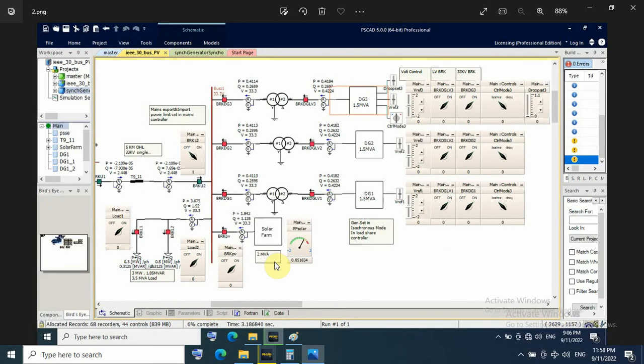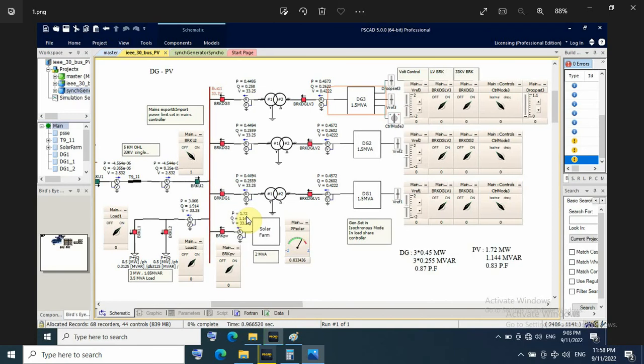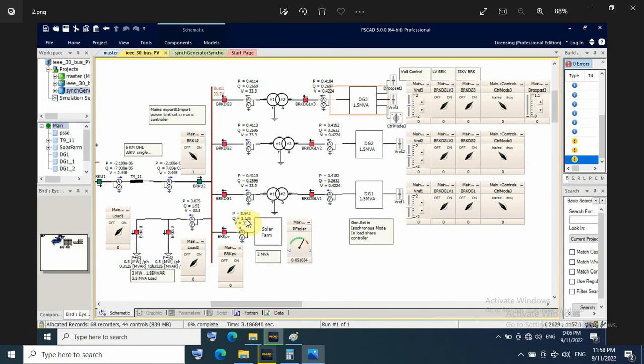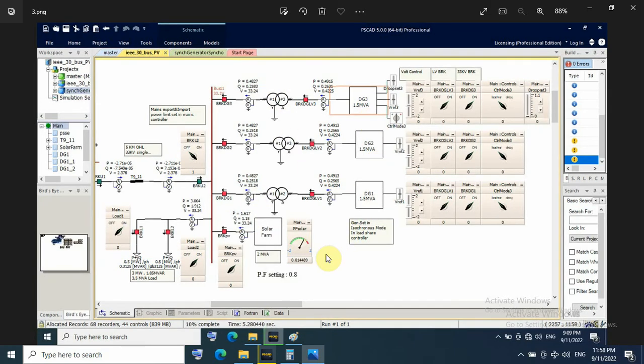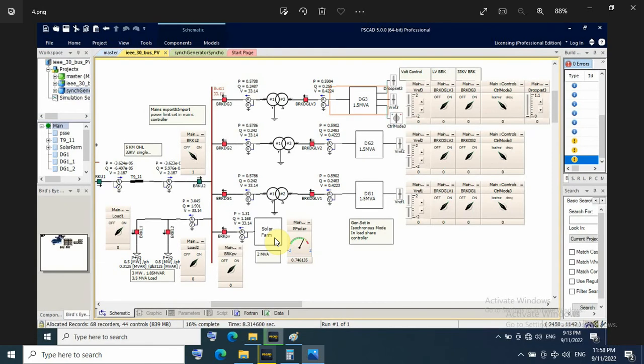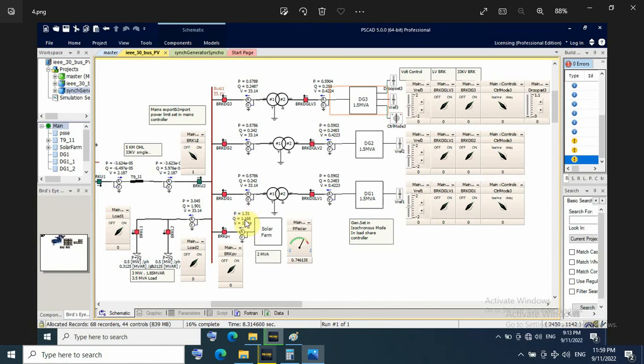Next. Here just only the PV generation increased to 1.8. The genset is stable. And here solar farm start to decrease the generation. Here 1.3. Now genset loading increased to 0.6 megawatt and 0.2 megavar for each genset. And PV generates 1.3 megawatt and 1.17 megavar at 0.75 power factor.